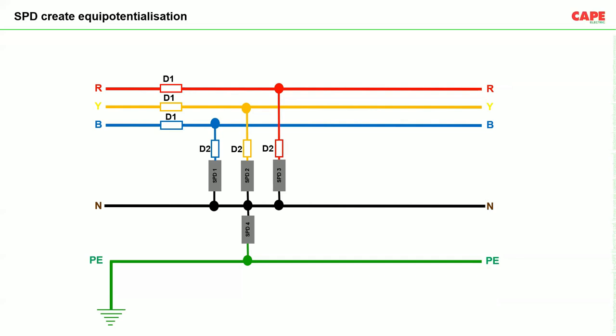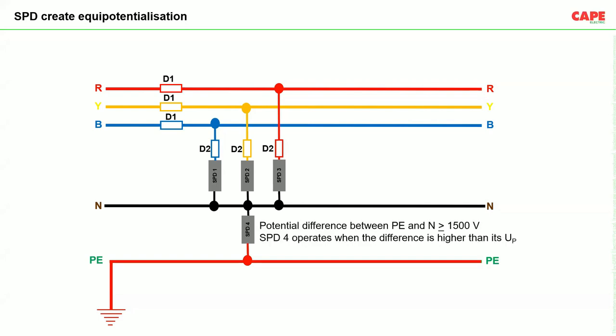Now, in a normal state, SPD is a parallel device with open circuit. Normally, it is in NO condition. It is not going to interfere in your system. Suppose there was a lightning strike or some other case, there was a surge through earth. Once there was a surge through earth, our earth will be at a very high potential. Let's say it was at 50 kilovolt. Now, since our earth is at 50 kilovolt, there's a potential difference between neutral and earth. If there was no SPD, because of this potential difference, your equipment is going to fail.